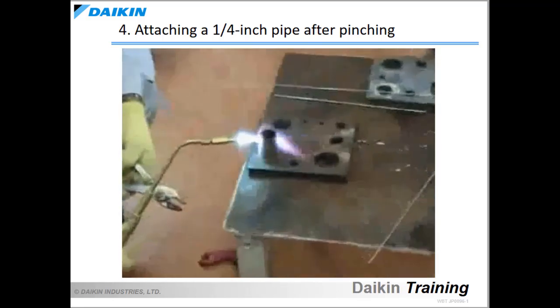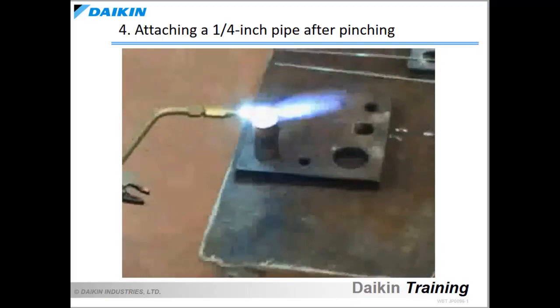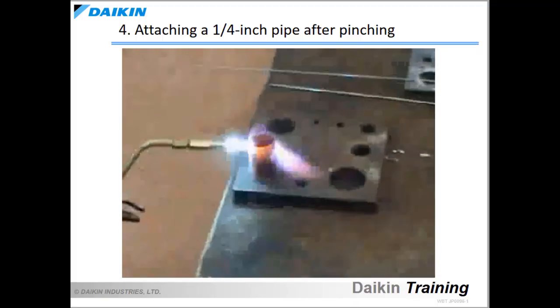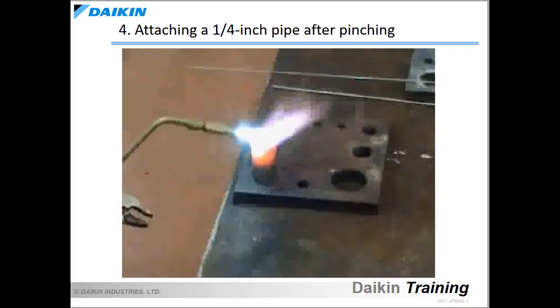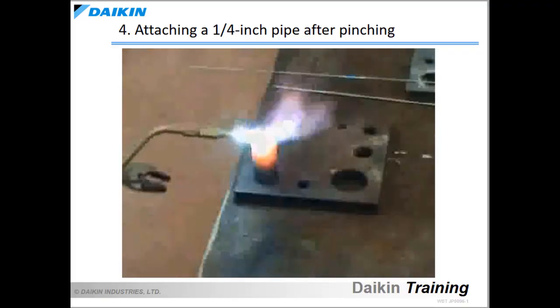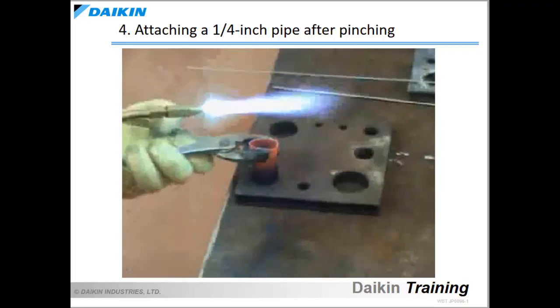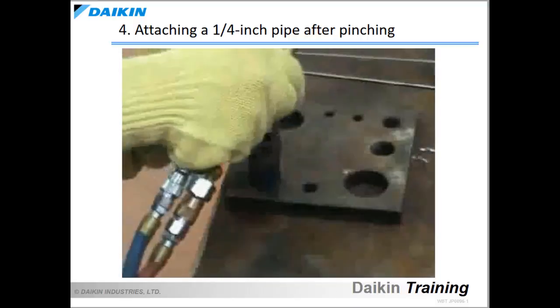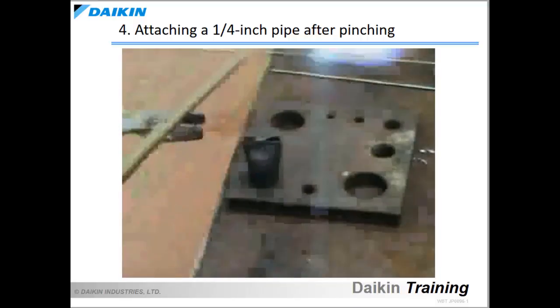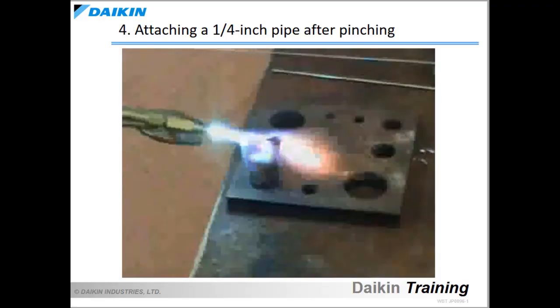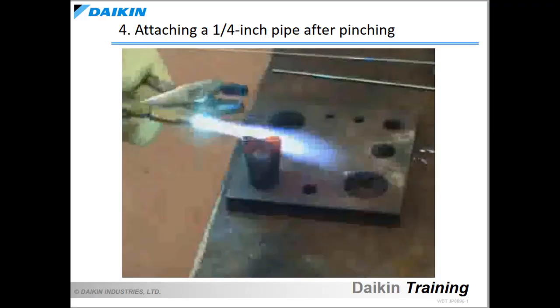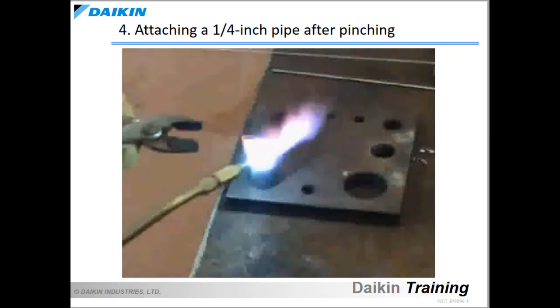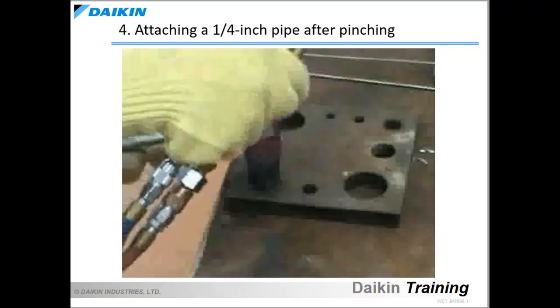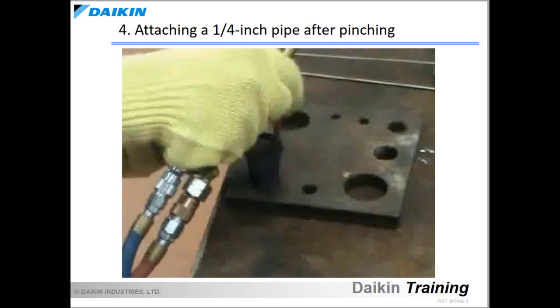Pinch the end of the larger pipe with pliers or the like, leaving a gap into which a 1/4 inch pipe can be inserted. Insert the 1/4 inch pipe approximately 0.5 inches into the larger pipe and pinch the larger pipe to reduce the gap. After heating the 1/4 inch pipe evenly, distribute the brazing filler metal into the connection area from the rear side. After closing the pinched gap on the large pipe by distributing the brazing filler metal, move the flame slightly away from the gap to create the build-up in a half-molten state.